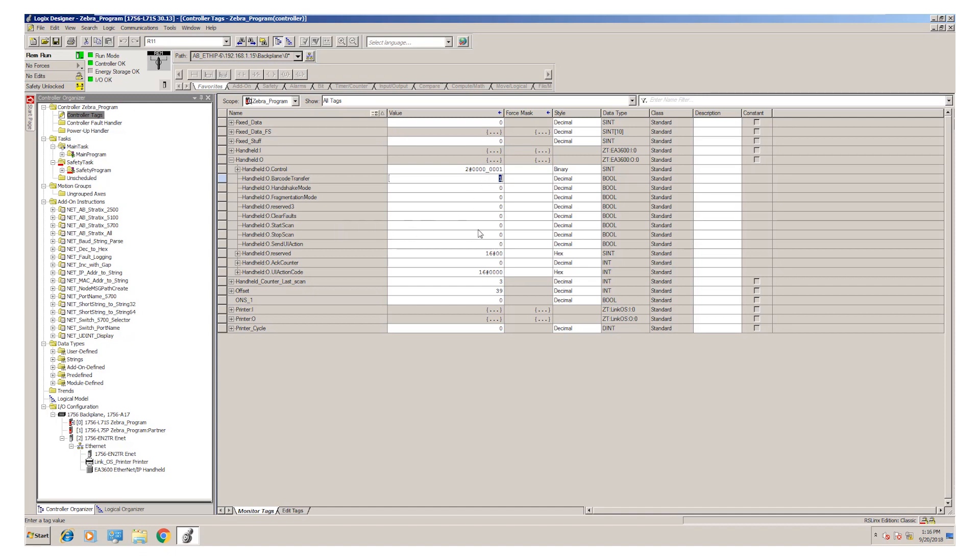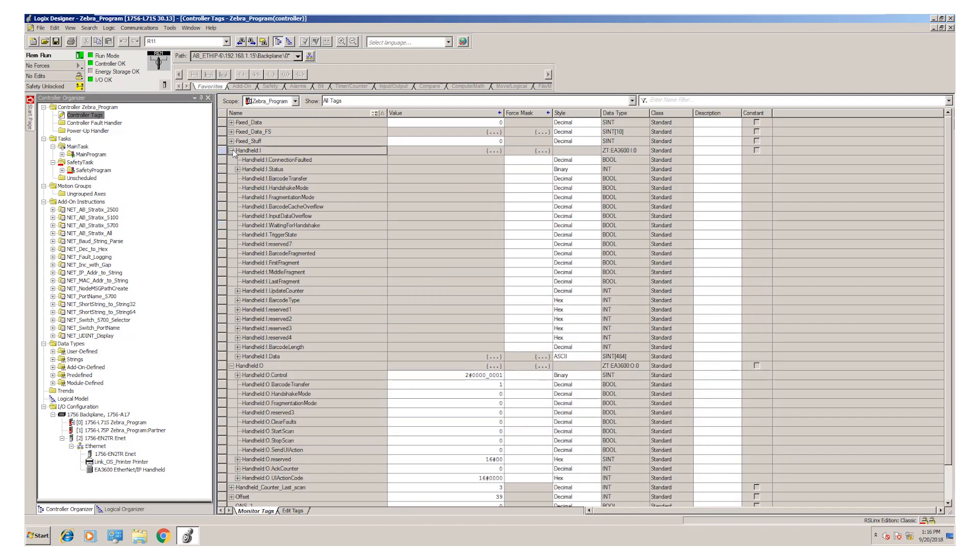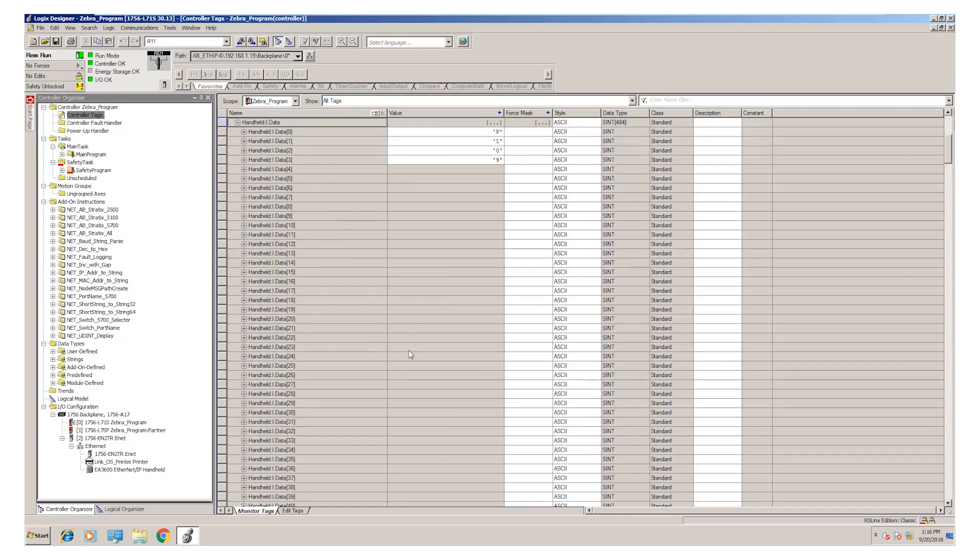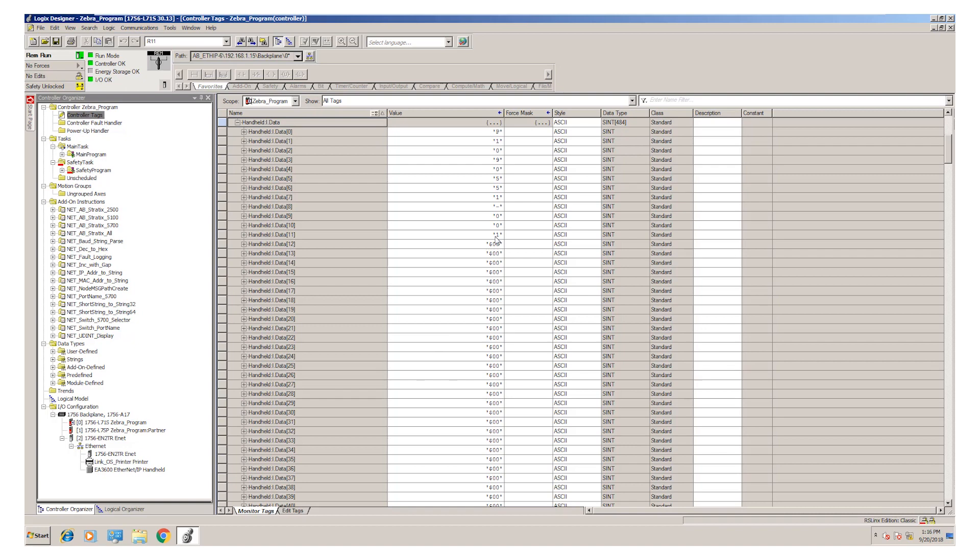The scanner is set up for a trigger on the handheld. If we wanted to make that automatic, we could set the start scan bit here and it will automatically trigger. Here you can see the status of the handheld. If we go to the bottom, we have a data field. This is where our data will show up once we scan a barcode, and then we can use that information wherever we want to in our program.